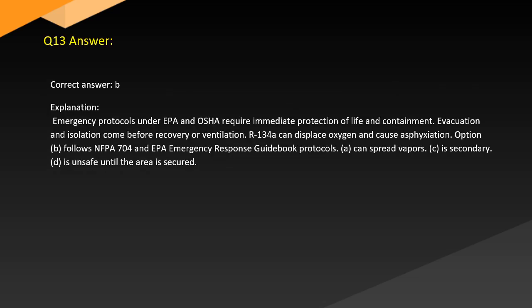Answer. Correct answer: B. Explanation. Emergency protocols under EPA and OSHA require immediate protection of life and containment. Evacuation and isolation come before recovery or ventilation. R134 can displace oxygen and cause asphyxiation. Option B follows EPA and Emergency Response Guidebook protocols. A can spread vapors. C is secondary. D is unsafe until the area is secured.